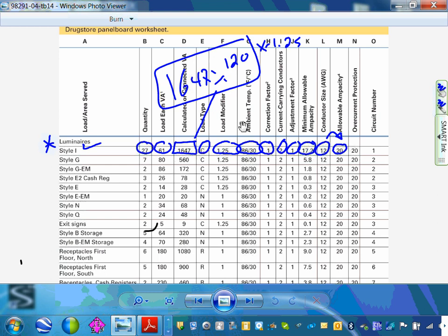Okay, now number 12, under normal operating condition, how much current can number 12 carry? You go to 240.4(D). No, it's right here, just the table, under the 60-degree column. 20 amps. Well, I'll just double check. The 3 stars will tell you guys. You want to take that into account, or? Yes, the 3 stars will tell you number 12 cannot be protected for more than 20 amps.